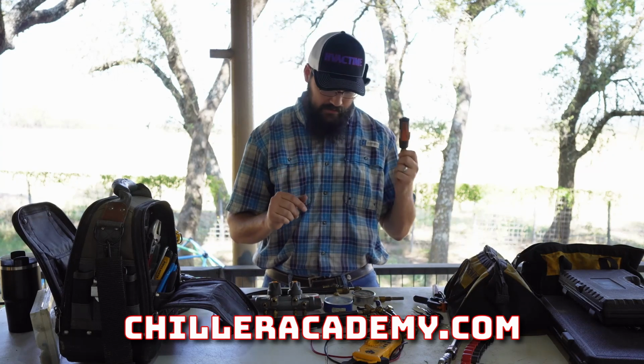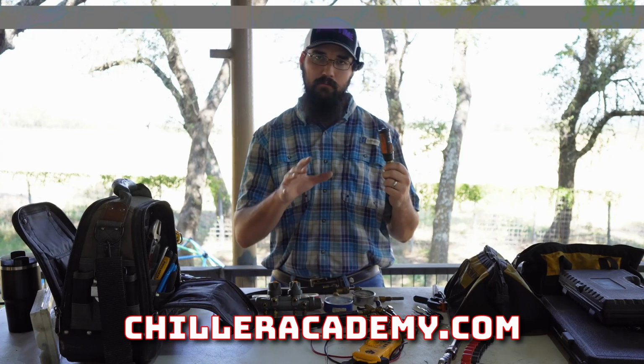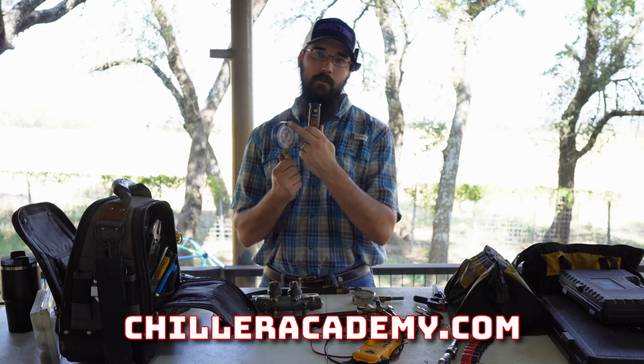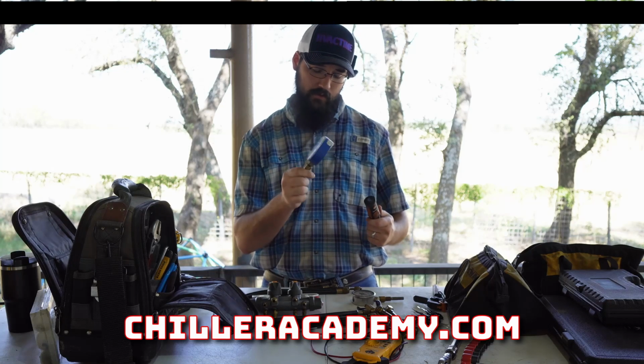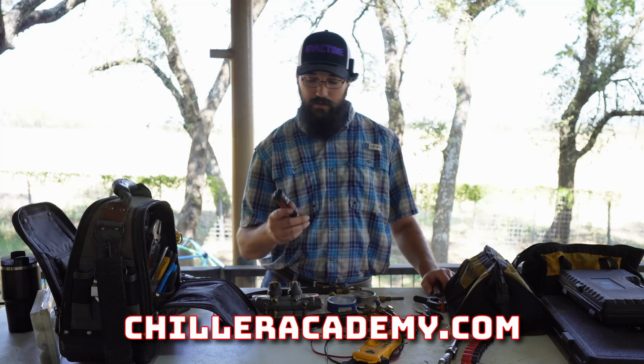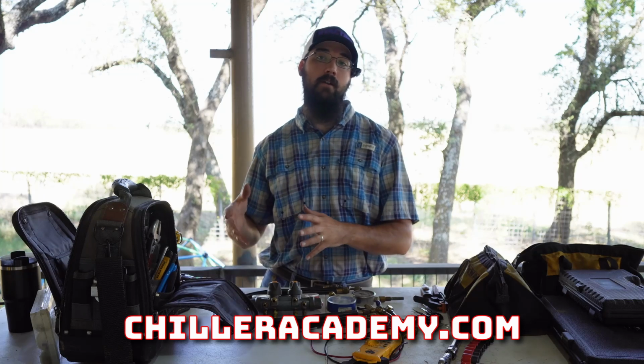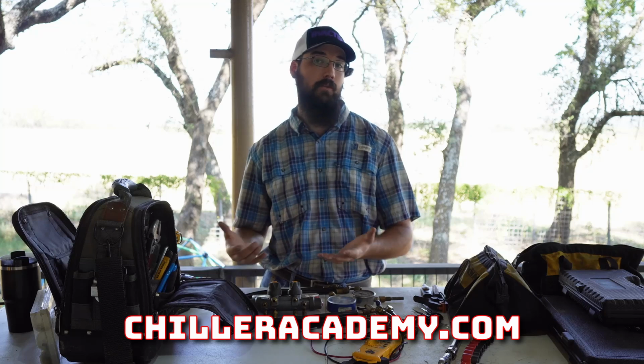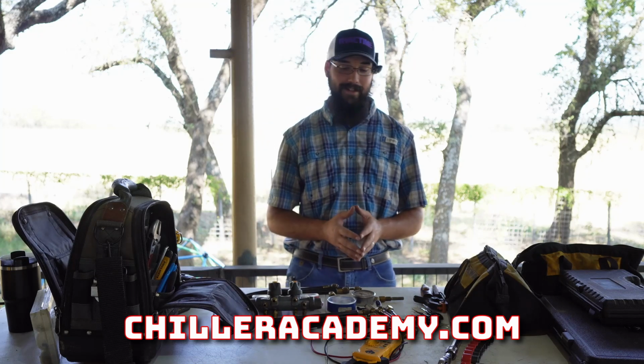Now, I do find that these are easier to test on low pressure systems. I'm saying like in a vacuum, low pressure chillers, compared to an analog. Now they make analogs that were vacuum, the green portion, inches of water. They make those that are just for that. I never personally used a set. I started using these Bluetooths and using that to compare my low pressure readings to make sure my temp sensors and everything else were acting correctly was actually a really great benefit that I didn't expect to get out of them when I bought them.